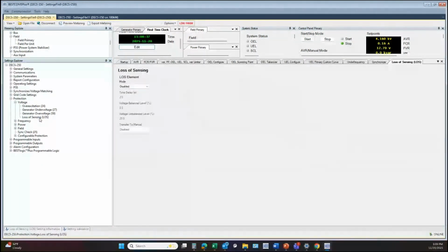But some of the more important ones are like the loss of sensing. We do recommend using the loss of sensing. If the DECS loses the ability to sense generator voltage, it can actually let you know that, and you can set it up to transfer to manual. So it transitions over to FCR control and allows you to continue operating, as I mentioned earlier, until something else trips you offline. Maybe you're perfectly fine running at that level until you add load, and suddenly, because you're in manual control mode, if nobody else adjusts excitation, as you add load you would see your generator voltage starting to drop. You would have some other protective relay trip you off then, rather than immediately having to trip off simply because the DECS lost the ability to sense voltage. So that can be and commonly is set up to transfer to manual.